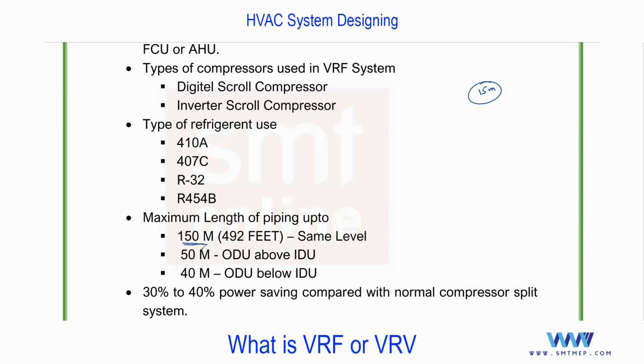But in this also we have points to discuss. 150 meters in what case? If the outdoor and all the indoor units connected are at the same level, suppose the building is only a ground floor and the outdoor unit is on the roof, that is almost the same level, the outdoor unit and indoor units at the same level. So we can go up to 150 meters. This is in general. Again, this may vary from make to make. Most manufacturers are offering this. This is the first point.